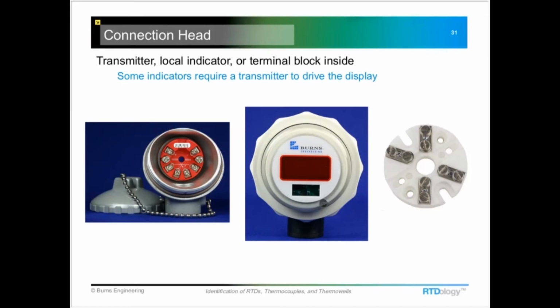Now inside this head there may be, as I mentioned, a transmitter like this. Certainly note that. If there are any identification marks on it, that helps let the manufacturer identify it. Some will have an indicator. You may open it up and just find the terminal block.